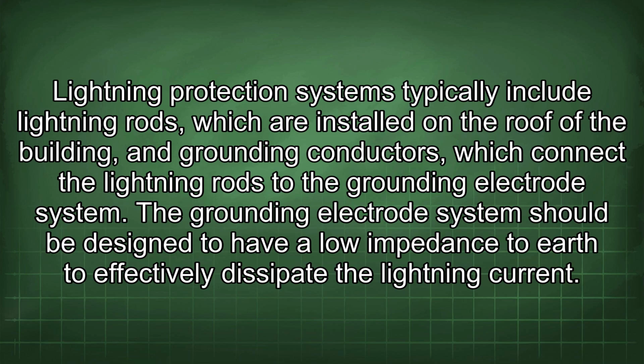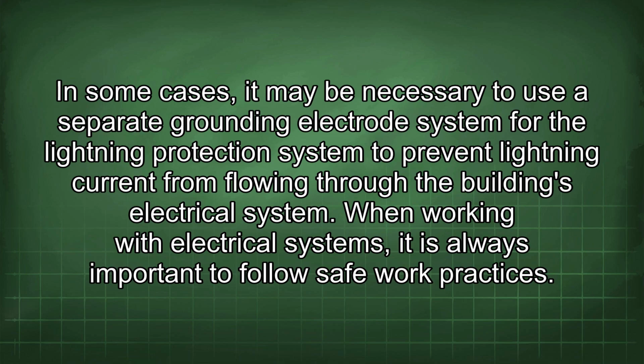The grounding electrode system should be designed to have a low impedance to Earth to effectively dissipate the lightning current. In some cases, it may be necessary to use a separate grounding electrode system for the lightning protection system to prevent lightning current from flowing through the building's electrical system.